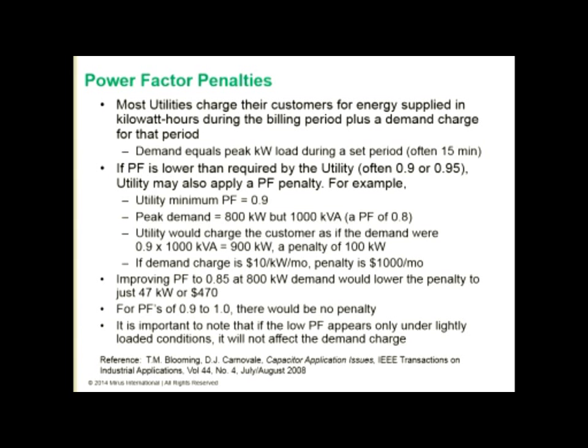So if we improve the power factor in this application to 0.85 and we maintain the same load at 800 kilowatts, this would lower the penalty to just 47 kilowatts, or $470. Because essentially 800 kilowatts divided by the power factor of 0.85 is 941 kVA, and 0.9 times 941 kVA is 847 kilowatts. So the difference between the actual real power of 800 and the penalty is 847 minus 800, or 47 kilowatts. For power factors that are 0.9 or unity, there would be no power factor penalty.